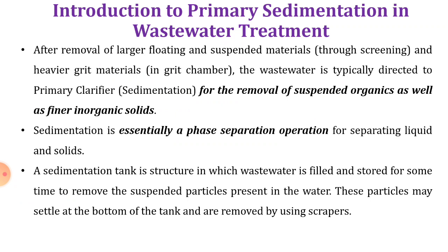After removal of larger floating and suspended material through the screening and the heavier grit material in the grit chamber, the wastewater is typically directed to the primary clarifier, which is called a sedimentation tank, for the removal of suspended organic as well as the finer inorganic solids. Sedimentation is essentially a phase separation operation for separating liquid and solids.